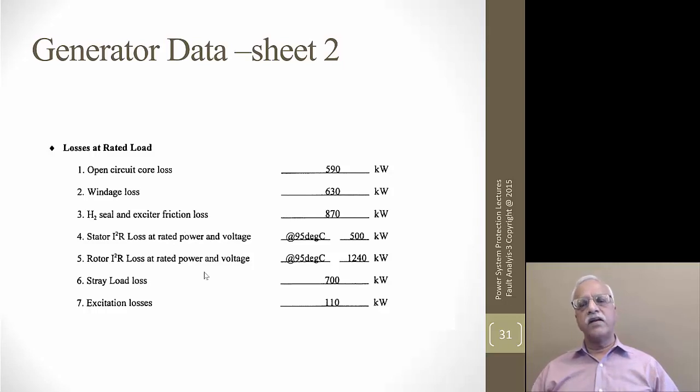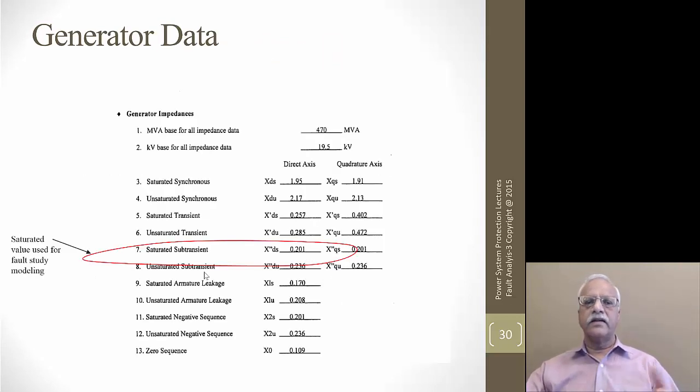So in short, when we looked at the modeling, we could easily measure the positive sequence, negative sequence, and zero sequence impedance of a transmission line, a transformer, a reactor, or a shunt capacitor or shunt reactor. But when it comes to the generator, we have to ask the generator manufacturer to provide the data, and they give you a test report that will have that. Similarly, for transformer impedances, they provide you a test report, and you use that. Whereas you know the impedance of shunt reactors and shunt capacitors, and that will be the positive, zero, and negative sequence reactances. That is very straightforward.